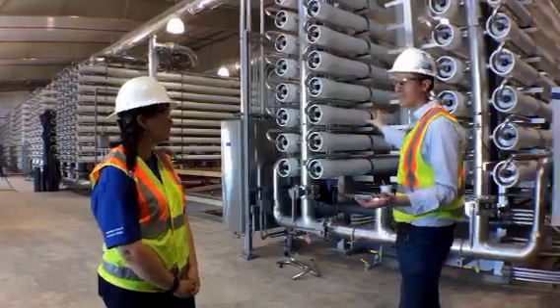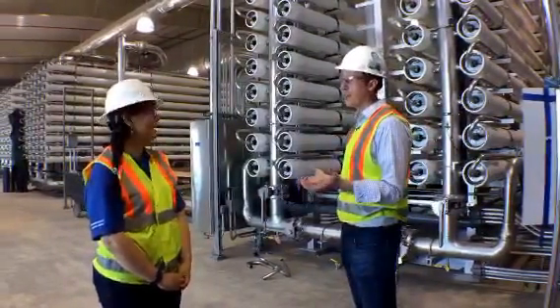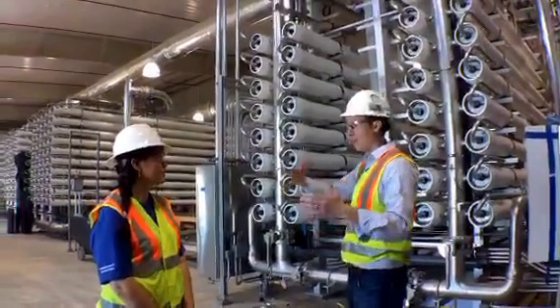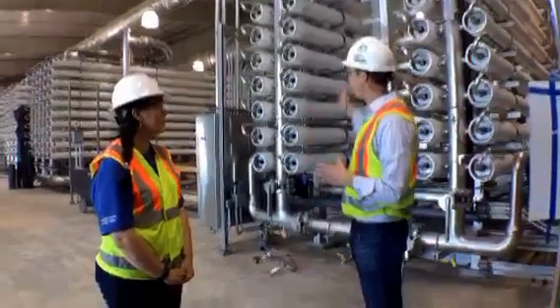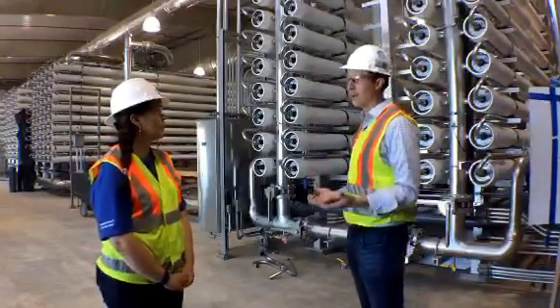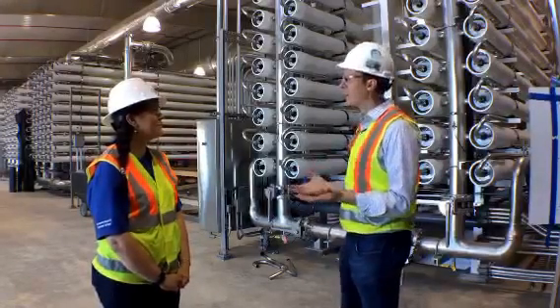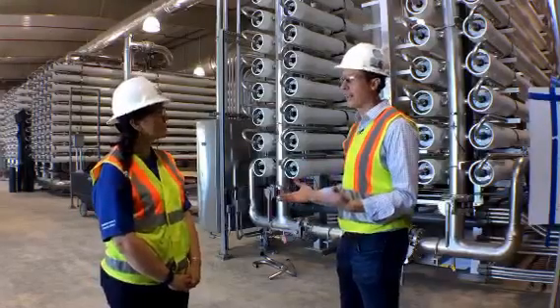This white portion — just some terminology — is called a vessel. It's the housing of the membranes. Within each vessel we're going to have seven membranes. They're spiral wound, about 40 inches long and eight inches in diameter. For all this area here we're going to have over 1,900 membranes total. These membranes tend to last five to seven years if you do a good job cleaning them.